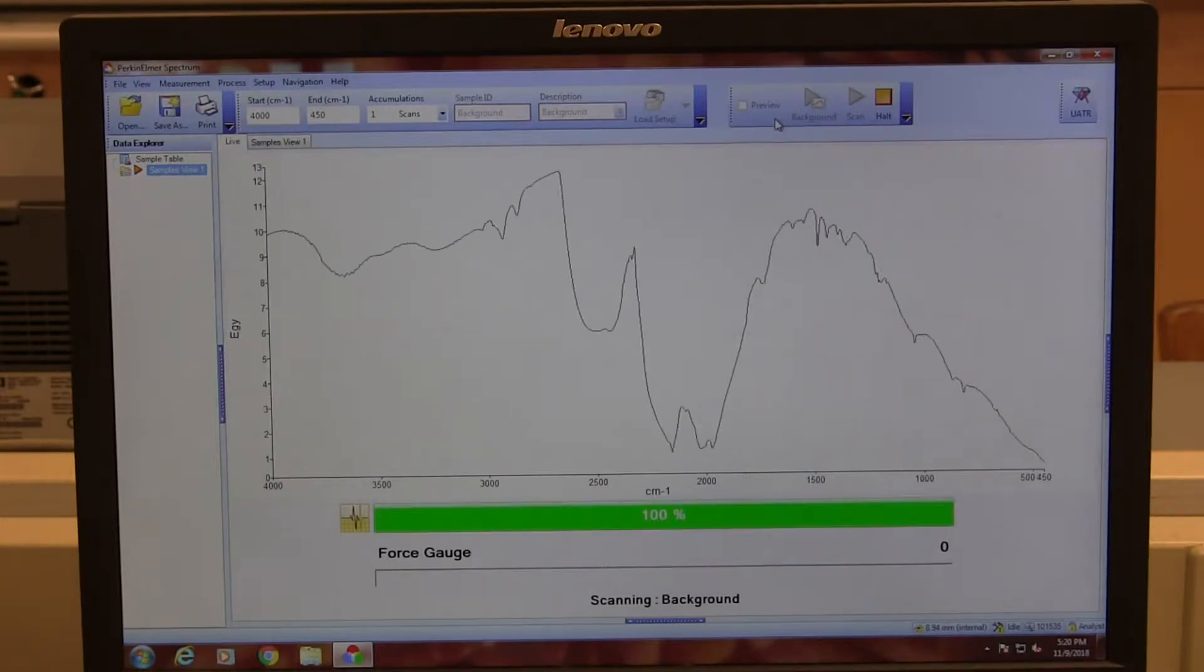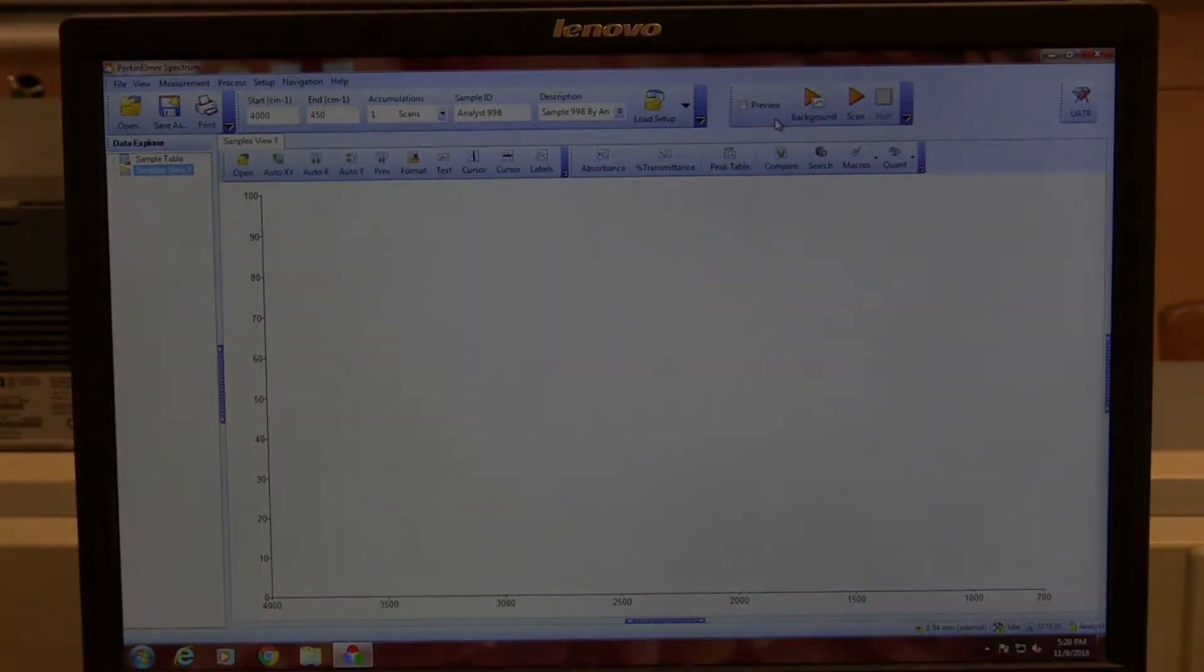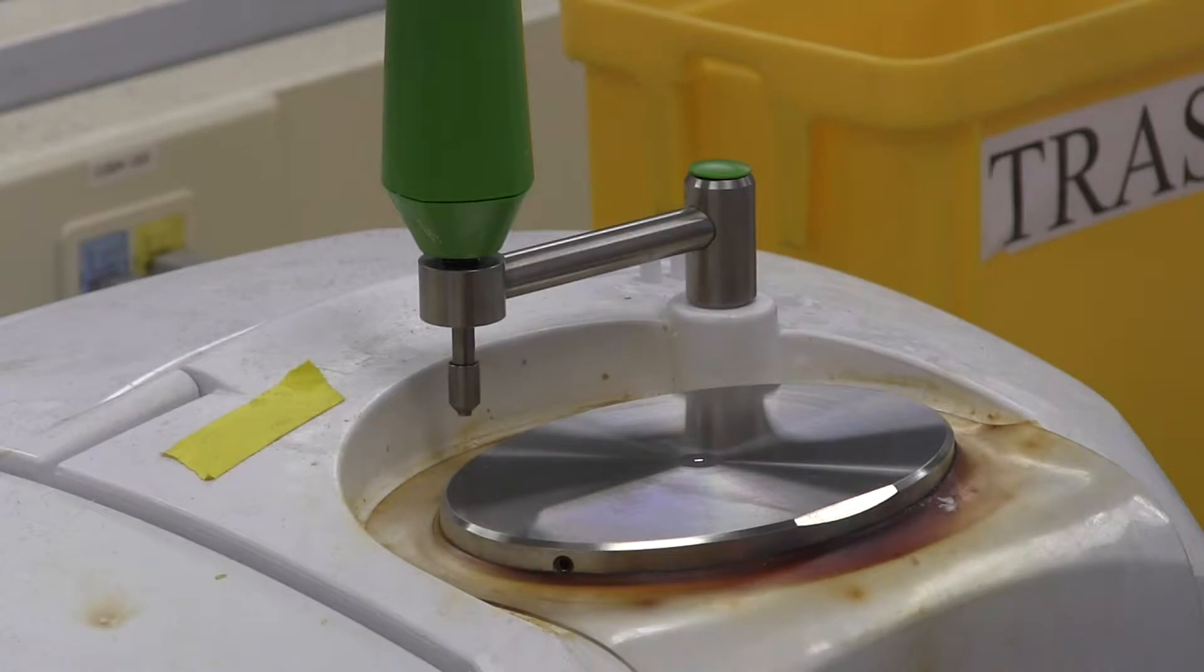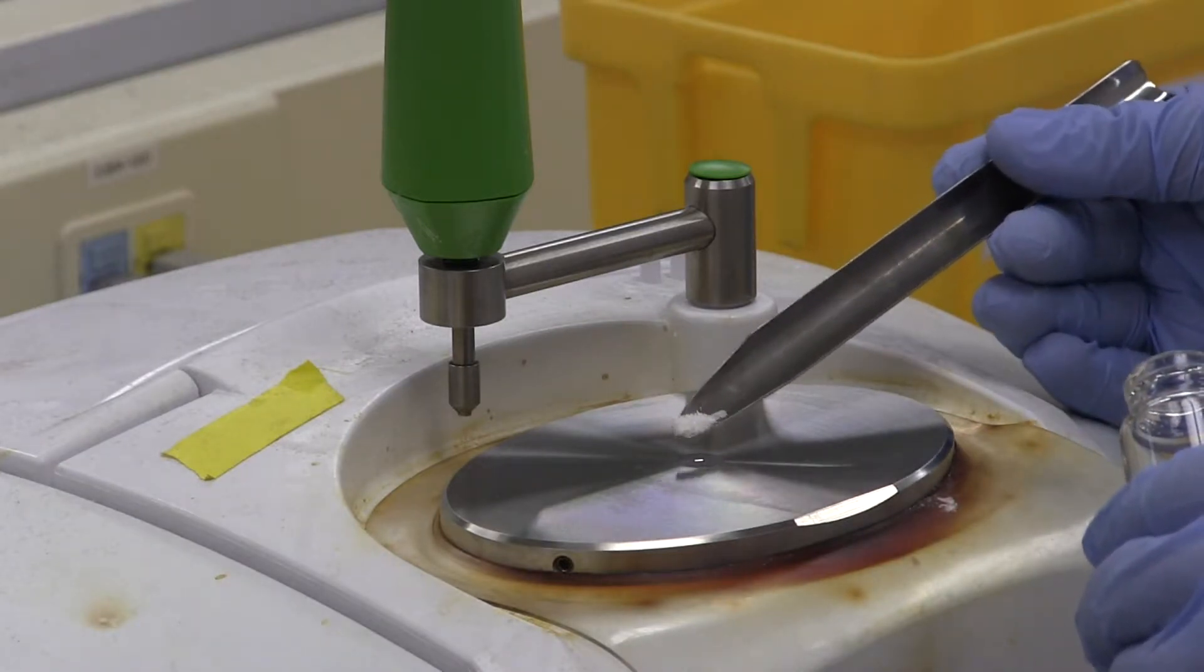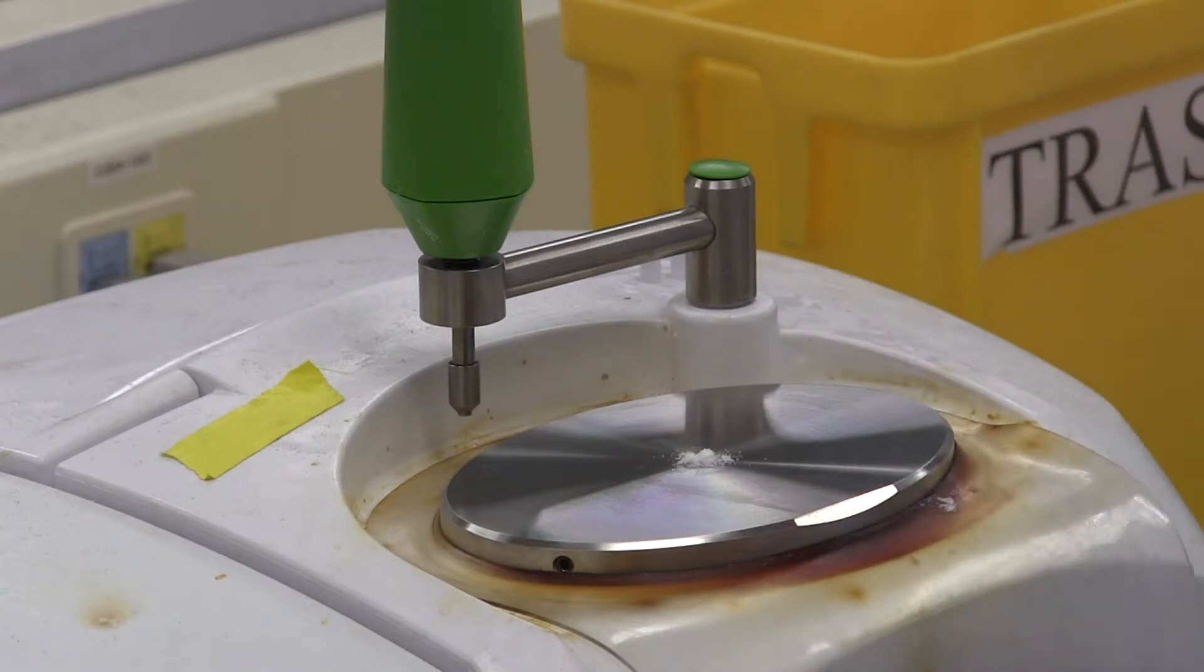Now we can begin to add some of our sample to the spectrometer. When adding the sample to be analyzed, it is important to avoid using too much material. Just make sure to cover the crystal with sample and turn the knob on the arm so that it presses firmly against the sample.